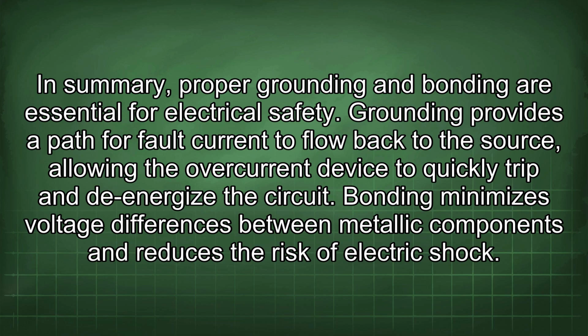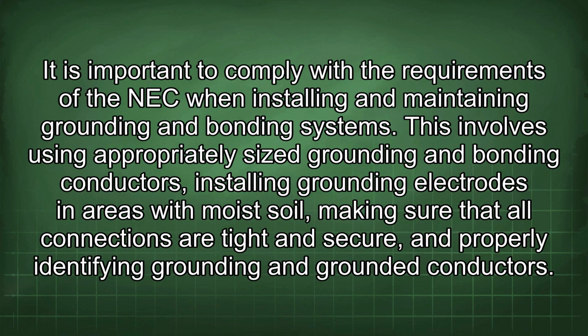In summary, proper grounding and bonding are essential for electrical safety. Grounding provides a path for fault current to flow back to the source, allowing the overcurrent device to quickly trip and de-energize the circuit. Bonding minimizes voltage differences between metallic components and reduces the risk of electric shock. It is important to comply with the requirements of the NEC when installing and maintaining grounding and bonding systems. This involves using appropriately sized grounding and bonding conductors, installing grounding electrodes in areas with moist soil, making sure that all connections are tight and secure, and properly identifying grounding and grounded conductors.